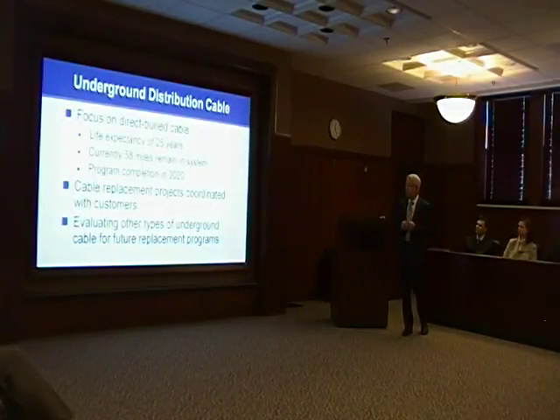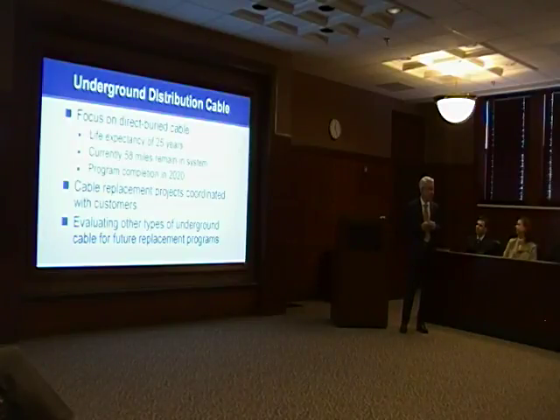Underground distribution cable, our focus has been on direct burial cable, and it's been on that program since Century 2 began. The life expectancy of direct burial cable is less than it is if it's in conduit. You would say, well, that makes sense because it's out of the environment. It gives a little bit of space around there to help the cooling effect of the cable, because anybody knows that electrical components heat up, and heat is the enemy of any electric component.